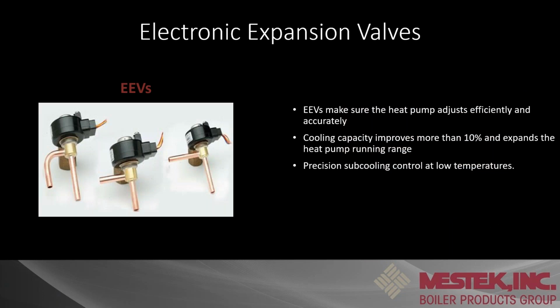On top of that, we have electronic expansion valves, so EEVs. The reason for electronic is that you have an inverter compressor that is modulating, so we also need the expansion valve to modulate with it accordingly. Your standard expansion valves, TXVs, are typically wax and spring driven based on temperature. These are driving based off temperatures they're reading from each part of the refrigeration system and adjusting accordingly.